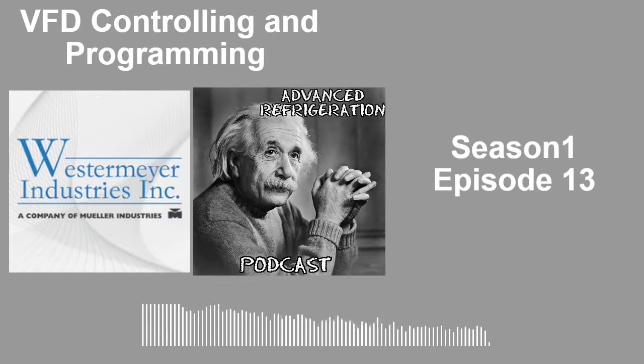Certain compressors get harmonic vibrations at certain frequencies. Now, these drives are great. They're advanced. You can delete frequencies out of drives and make it skip. I go through these stores and do this all the time on CO2 stores. I'll be tuning them. I see it more on CO2 stores than anything else.